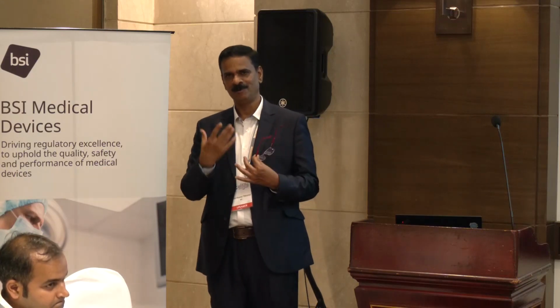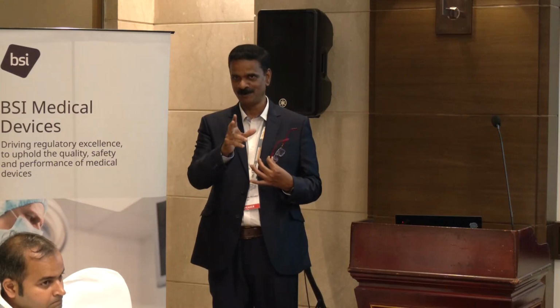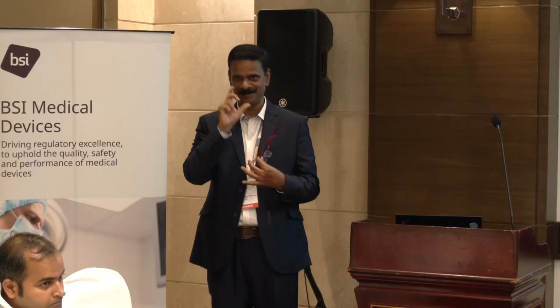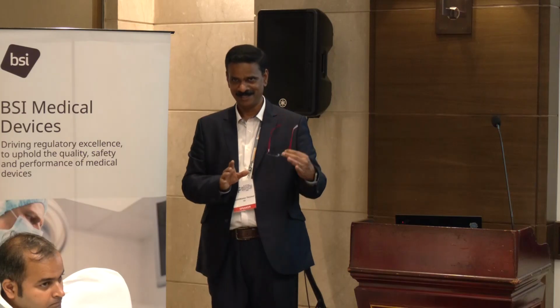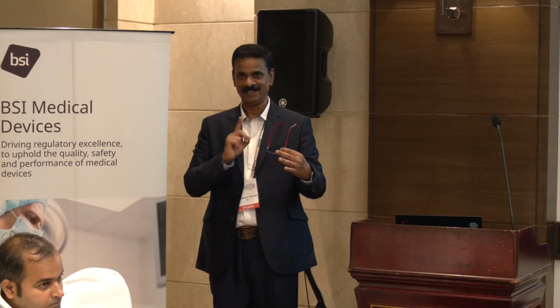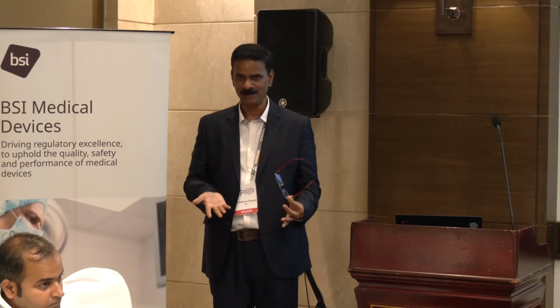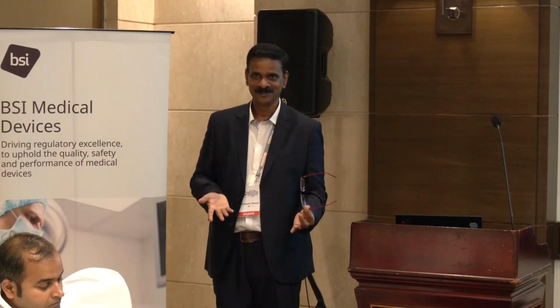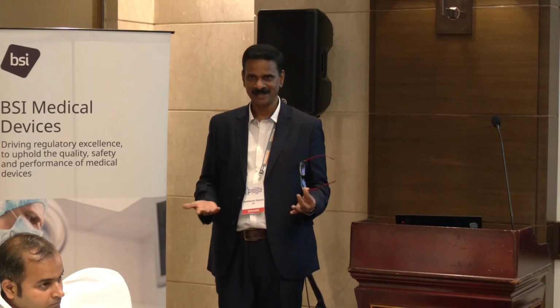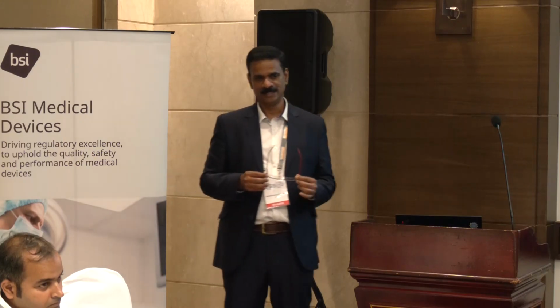I am not a dialysis specialist, but with the information you gave, I can immediately see it is a big design change, where it is mechanical going into electrical and electronics. So that definitely needs additional reviews. It may impact clinical performance, and I don't know about safety also, right? What software validation you have carried out, all this work is up to you to do.